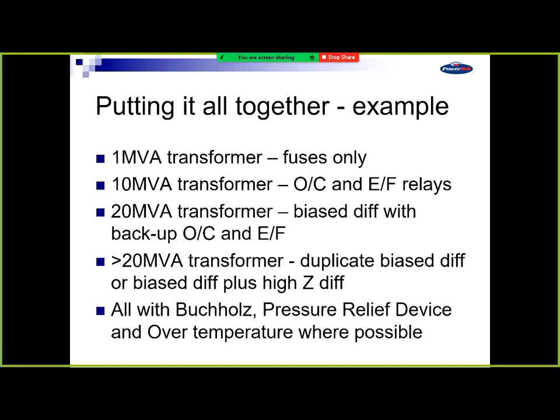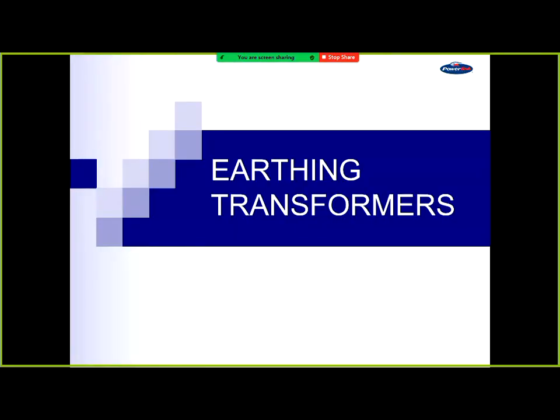But that's not common. No, it's not common, but we've got about 3 or 4 of these really little transformers that have connected to our network, because we've got electricity in the townships 100 kilometres away. So it's too far to run a 11 or 33 kV feeder. You just have big voltage drops at the end, and it's very costly to do that.